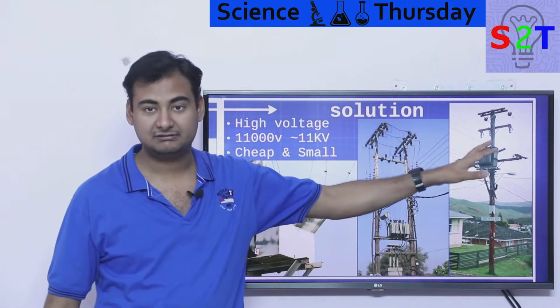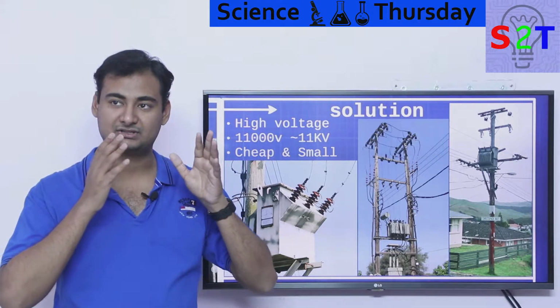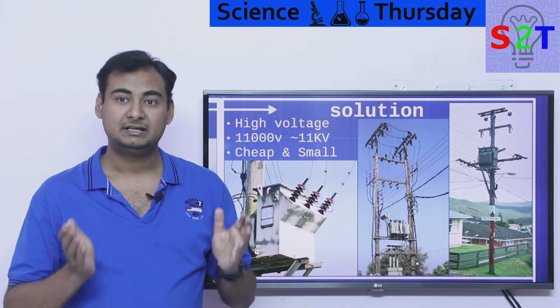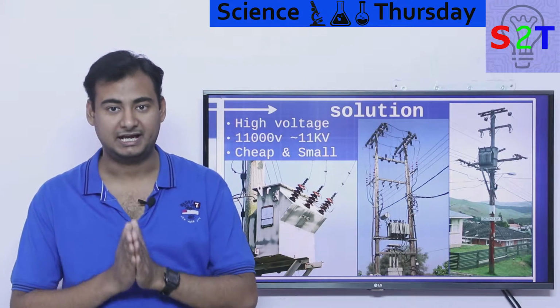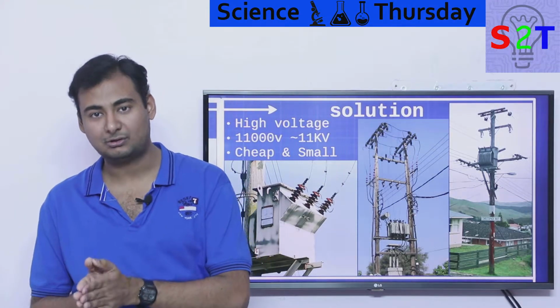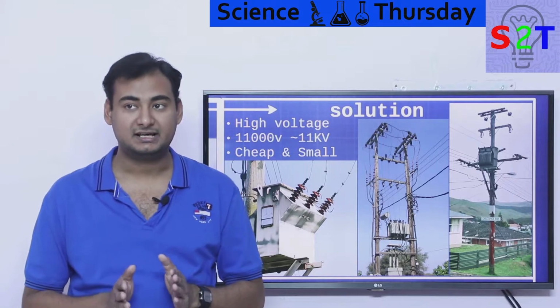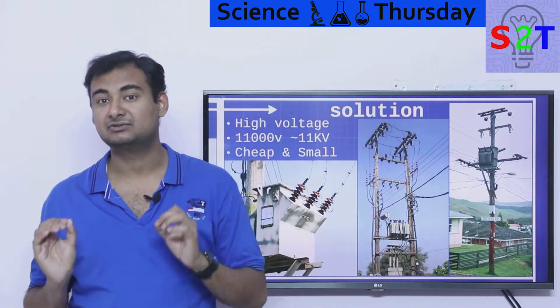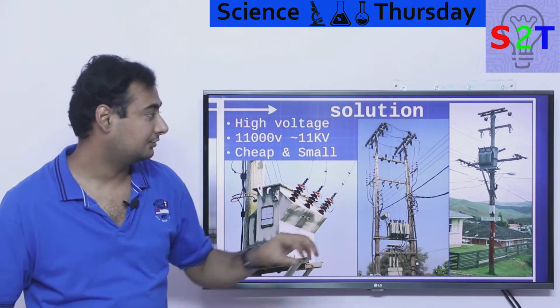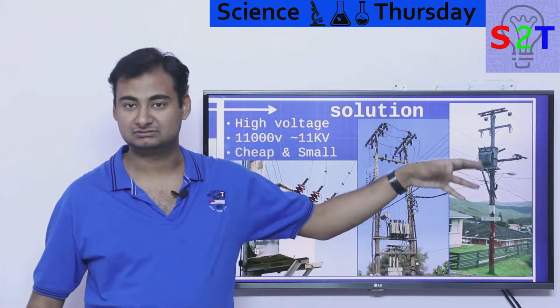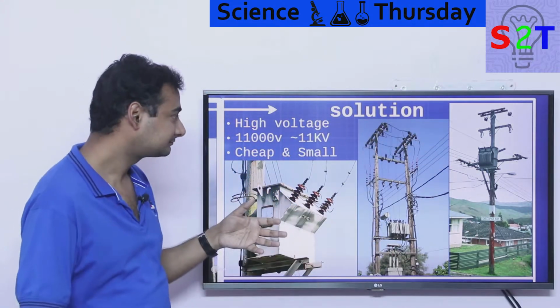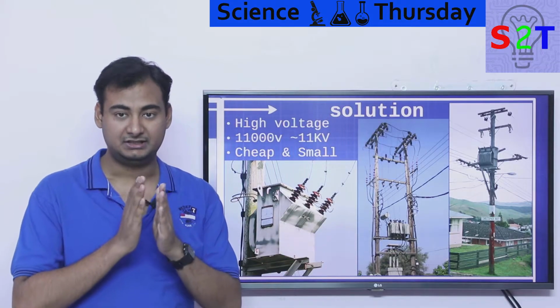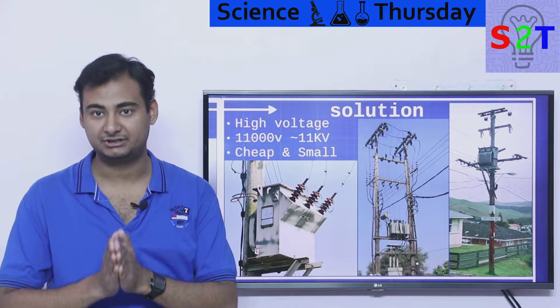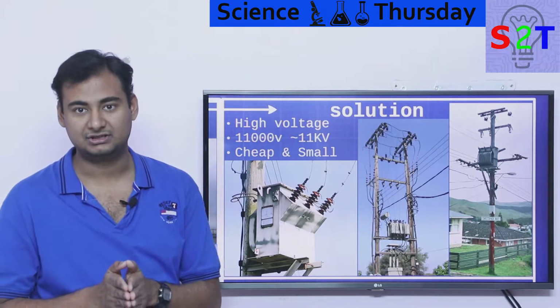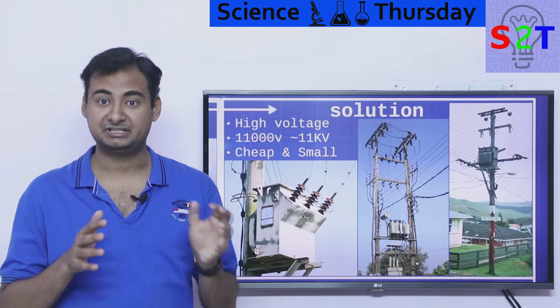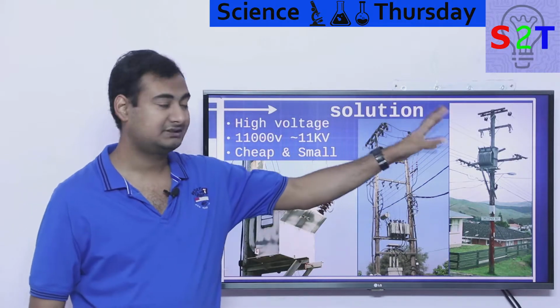So for a neighborhood, 11 kV is a good compromise. Basically, the voltage is not so low that the ampere would be too high, and it's safe enough, as in the air's dielectric strength, basically the air's ability to stop the electricity jumping from one point to another, is high enough. You also have to take rain into consideration, because we cannot afford to put sheathing, basically insulation, on these lines. It would be way too expensive. So with all that considered, is the voltage high enough to reduce amperage? Is that voltage manageable by air in a wet, rainy environment? Yes, then we settle on 11 kV.